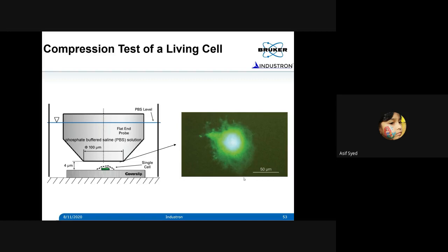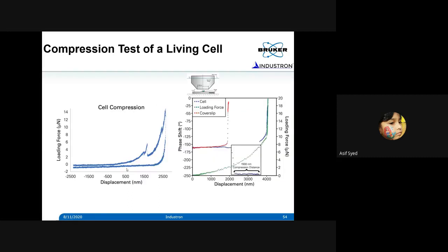Now, as I mentioned, making the contact and sensing the contact of the cell is a very challenging thing. When you make contact, you won't feel like you are sensing the contact. So that's why you need to use this phase approach. If you monitor the phase, for example, in this next slide, this is done in a submerged condition using a PBS solution. And in this, you see the whole probe is submerged, and you can see that the cell is just beneath the probe, and you are approaching with the probe to make contact.